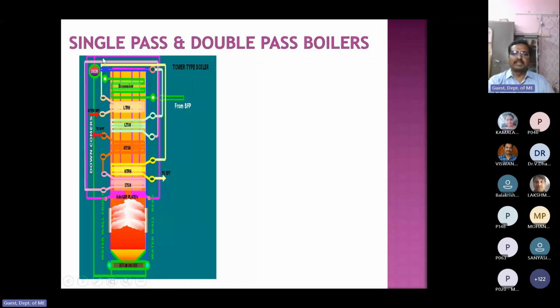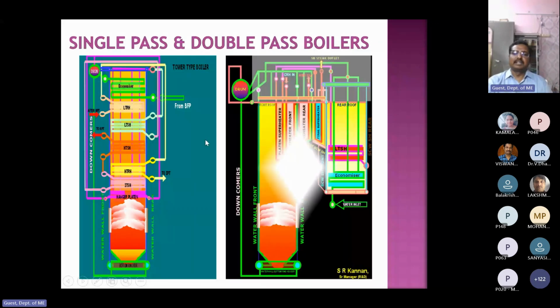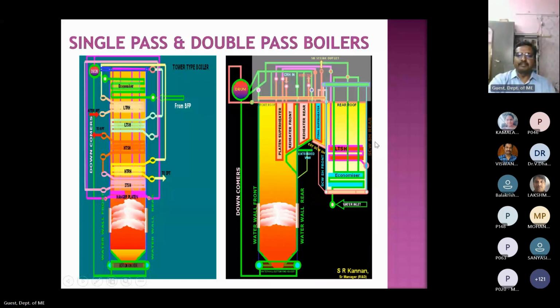Another type of boiler is the double pass boiler. Here some heat exchangers are arranged here and some heat exchangers are arranged here. The second pass is only the low temperature zone. Here the economizer and LTSH, meaning low temperature superheater, are arranged. This is called a two pass boiler. In our 210 megawatt boilers, we are using both types. In units 1 and 2, there are two pass boilers, and units 3 to 6 are single pass boilers. All are designed that way.